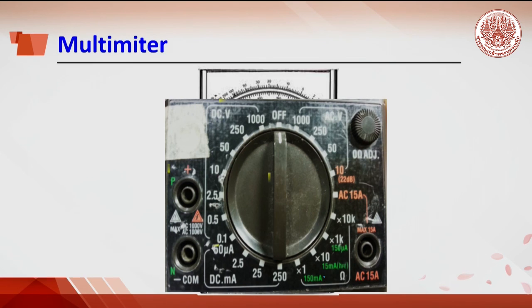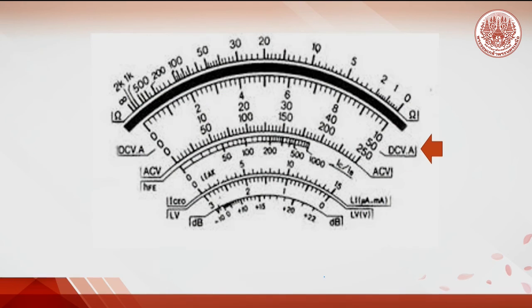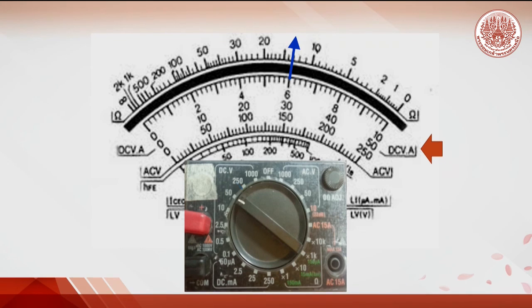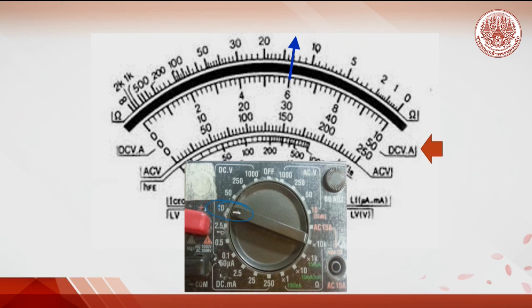The measuring range starts from 1000 down to 0.1 of the full scale. The scale being read is on DC voltage. The full scale can be maximum at 10, 50, and 250. For example, if the pointer is at a certain position and the measuring range is 250, the EMF recorded is 150 volts. If the measuring range is 50, the full scale is 50, so the reading is 30 volts. When the range is at 10, meaning the full scale is 10, we get an EMF of 6 volts.